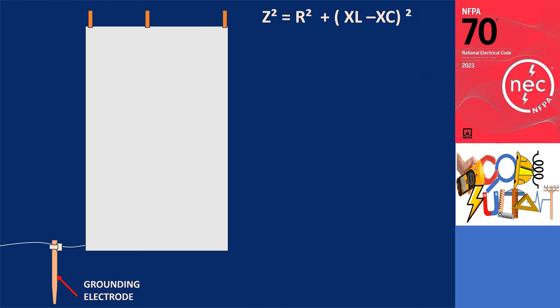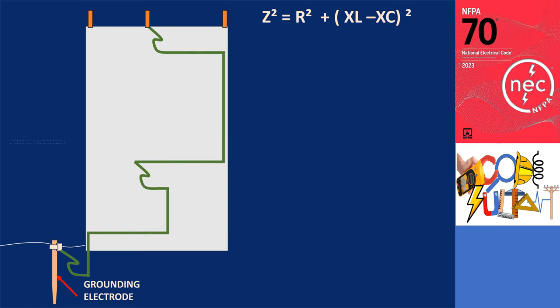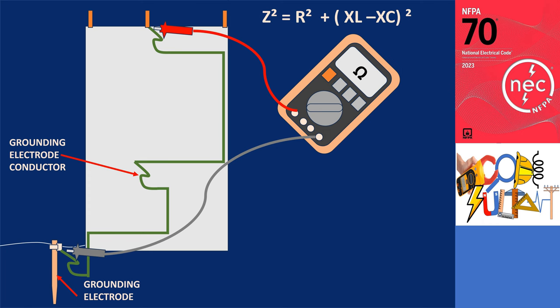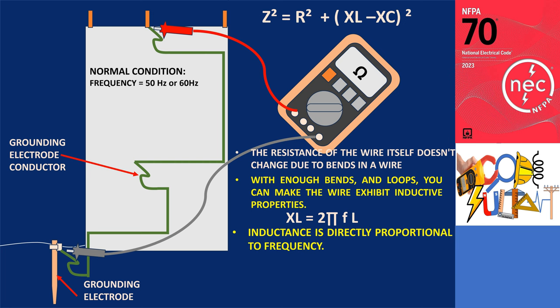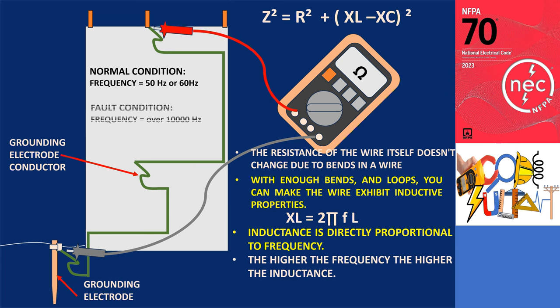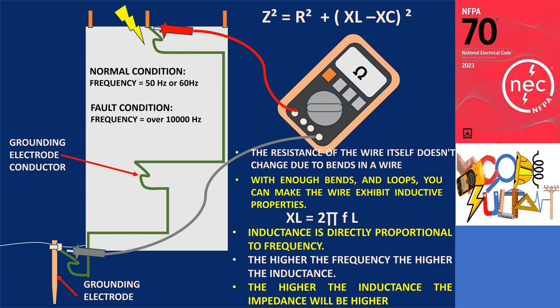Imagine a properly sized earth grounding wire that contains numerous loops and sharp bends. While the resistance remains constant regardless of bends, introducing multiple bends and loops can give the wire inductive properties — and inductance is directly proportional to frequency. While this grounding electrode conductor may be suitable for DC or low-frequency applications such as 50 or 60 Hz, during events like line surges, lightning strikes, or other transients with frequencies over 10,000 Hz, the impedance of the path will significantly increase.